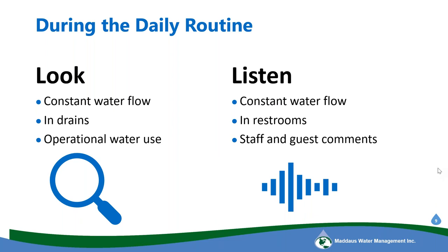Some equipment we won't be able to see as easily — it might be in a closet, or the drain might be under a shelf. So we'll also have to listen. I was working in a facility where the cooling tower was on the roof but drained inside the building and had a valve malfunction — it was flowing 30,000 gallons a day. You could hear it, but nobody knew what the drain was. In restrooms, you can poke your head in the door and almost immediately hear a running toilet. We can also ask staff and guests to report any constant water use to our attention.